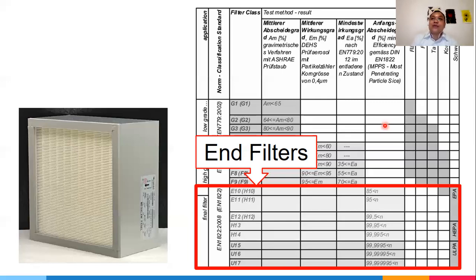So it depends on operating requirements. Some clients want their end filters at the terminal unit, others want them at the AHU. For example, semiconductors don't have end filters at their AHUs, they put it at the room itself. They have a fan filter unit where their HEPA filters are installed. So it depends on the client's requirement.